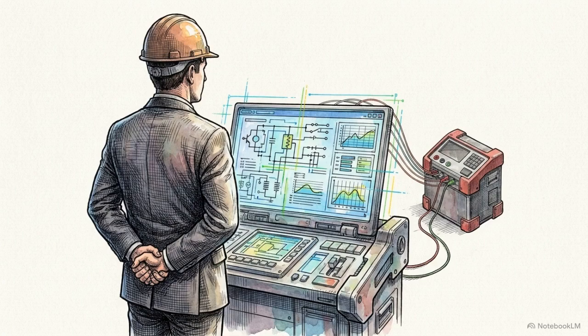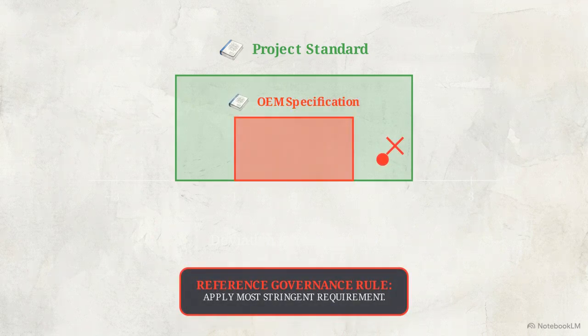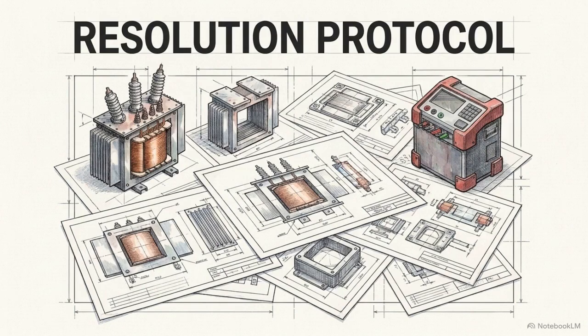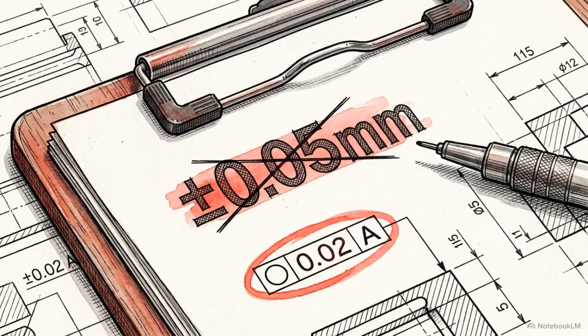The final challenge often occurs when interpreting the gathered data. Occasionally, a phase-to-phase test deviation might pass the broad limits of the project standard, but fail the tighter specifications set by the original equipment manufacturer. When this happens, the engineer defaults to the reference governance rule. They document the exact discrepancy, but immediately enforce the most stringent standard on the table.